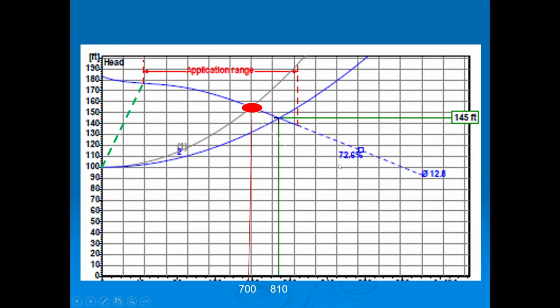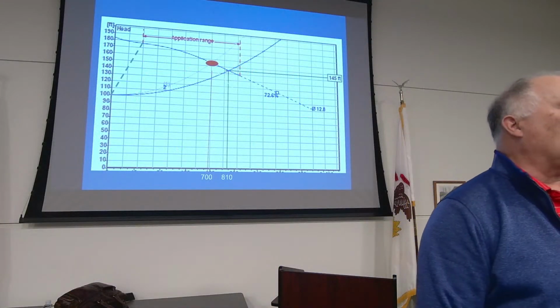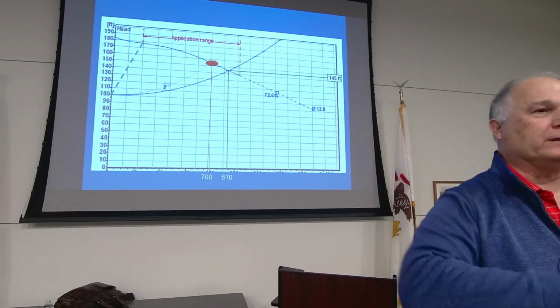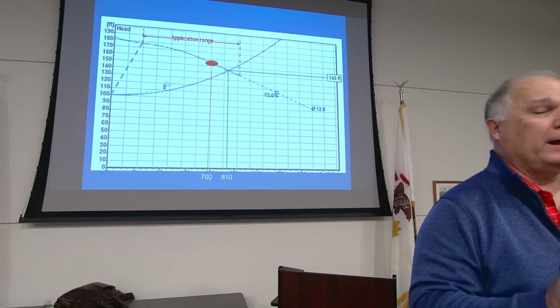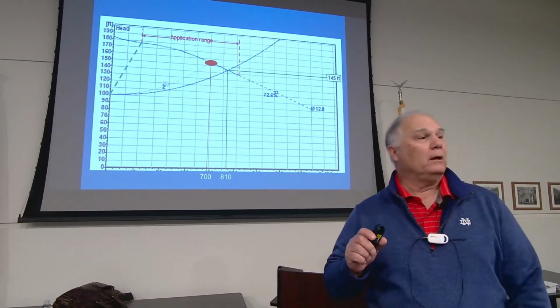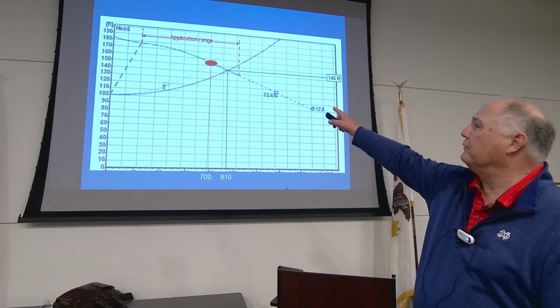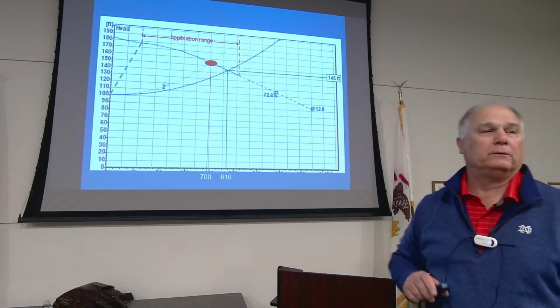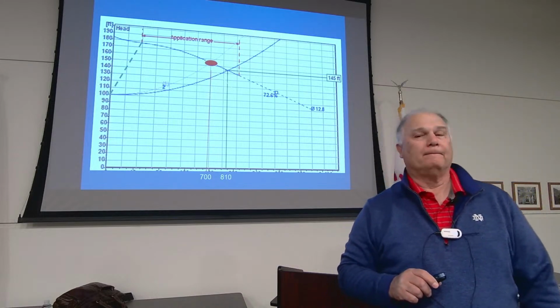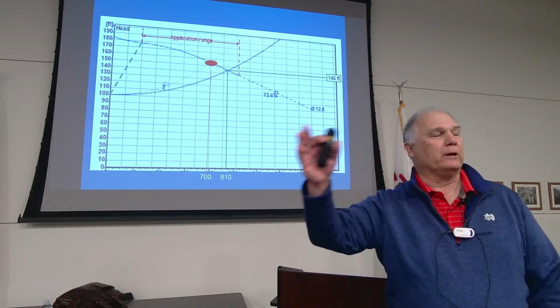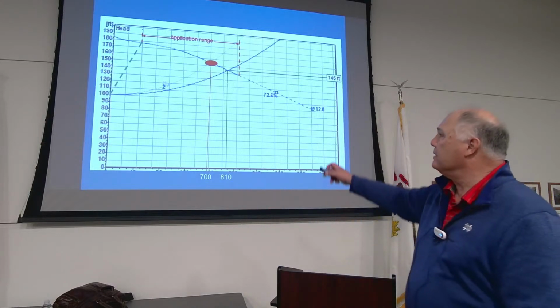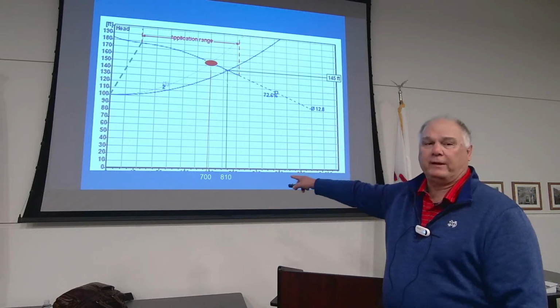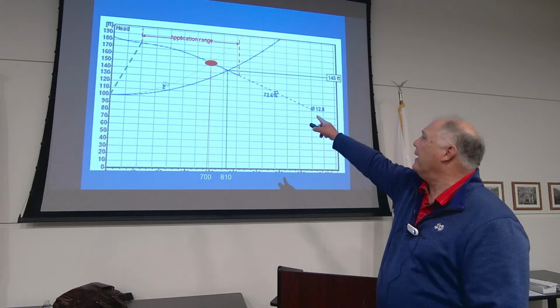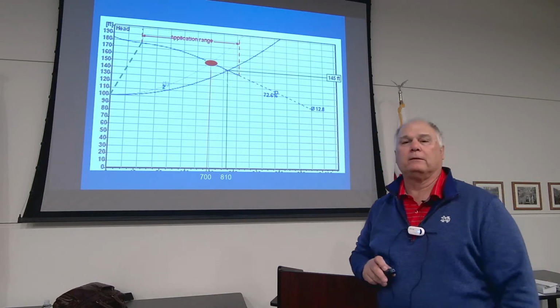We pick a pump, and let's say that pump is 20 horsepower. Perfect. We go out there, we start that station up, but our brand new pipe is not going to give us 150 foot, it's going to give us 140 foot. What's going to happen? We're going to give you more GPM. This is actually the condition we're going to give you. It's 810 gallons a minute at startup at 145 foot head.